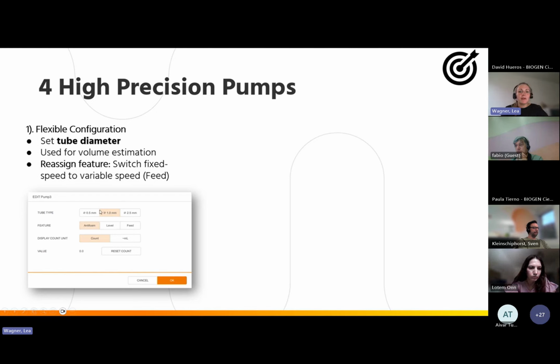So maybe if the customer does not need anti-foam, for example, because the cell culture does not create a lot of foam, or does not need acid because the customer has maybe carbon dioxide instead of acid, then the pump can be reconfigured as a feed pump. So it can be switched from fixed speed to variable speed, and this allows the customer to have an additional feed pump and to do, for example, more complex fed batch or continuous culture processes.